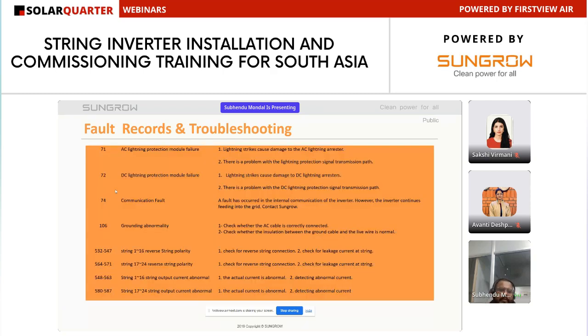Then 71 is AC SPD failure, caused by a lightning strike because it damages the AC SPD. 72 is DC SPD failure. 74 is communication failure. The inverter will be running fine, but communication will fail. It is a communication board issue. 106 is grounding abnormality. For this case, we have to check whether the AC cable is correctly connected or not.